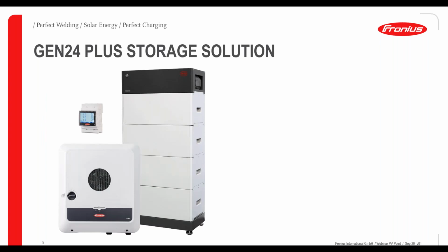What is the Gen24 Plus storage solution? Basically, it consists of three components. The Gen24 Plus inverters, in this case the Symo, in the power classes from 6 to 10 kilowatt, three-phase. So there's also an 8 kilowatt unit, three different power classes. These inverters come with 2 MPP trackers and also 1 battery input. Additionally, you need the Fronius Smart Meter, which measures the power at the feeding point and gives the inverter the information on what's actually going on there.